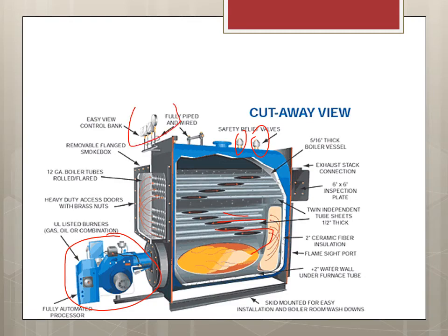Pressure controls tell you if we have high or low pressure, and this is where the flue gases go through the pipes to heat them and go outside to the exhaust. And let me see if they have, no, it doesn't show the controls here. I mean, this is my control over here, and this is completely automatic, and it should tell you what fuel is running. So they look the same, but some of them are different. If you look here, that's my flame proving signal.